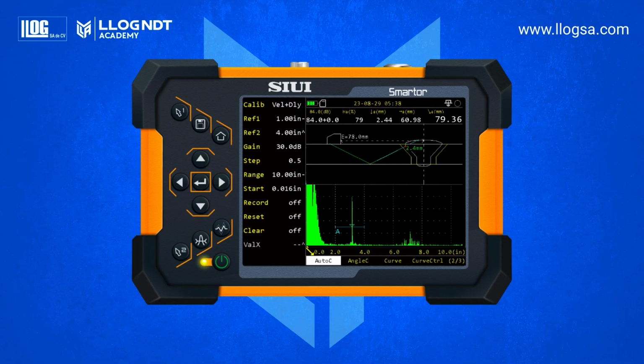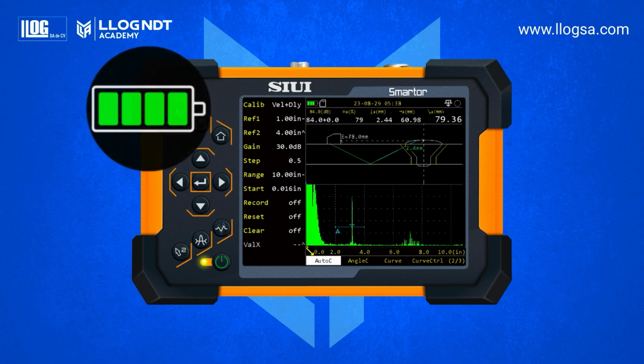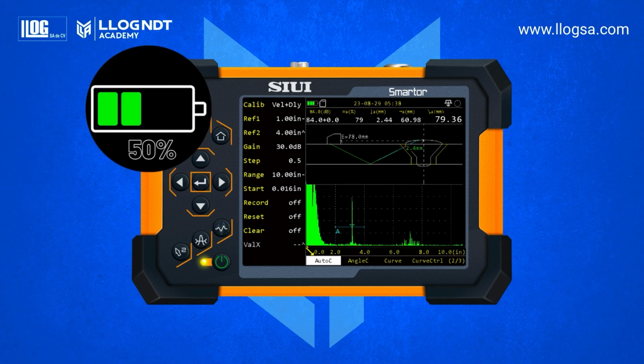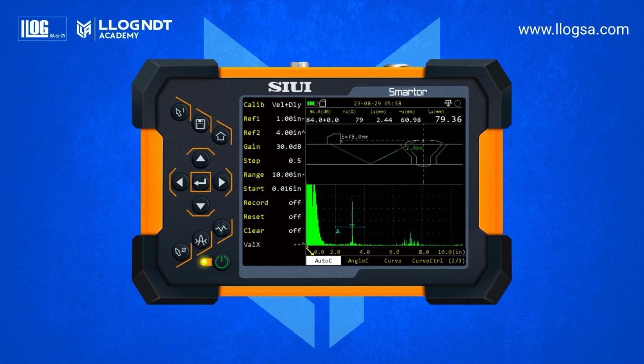Once the device is powered on and the UT mode is selected, we enter the main screen. We'll begin by reviewing the icon layout and the A-scan display. In the top left corner, you'll see the battery status icon. In this example, it shows a full charge. Each bar represents 25% of the total charge. If the device won't be used for a long period, it's recommended to power it on at least once a month and remove the battery.